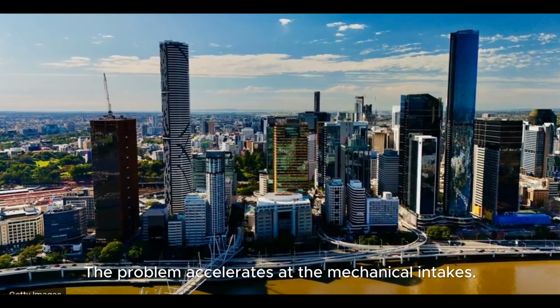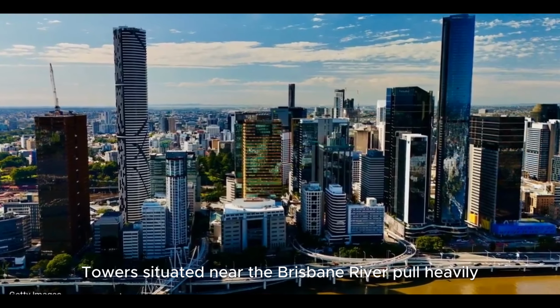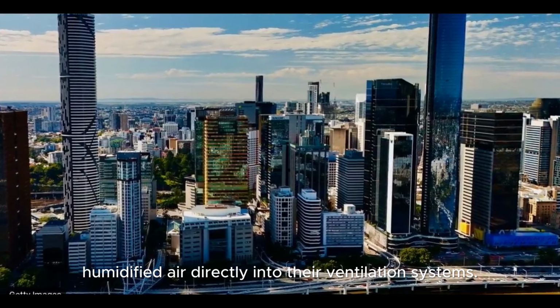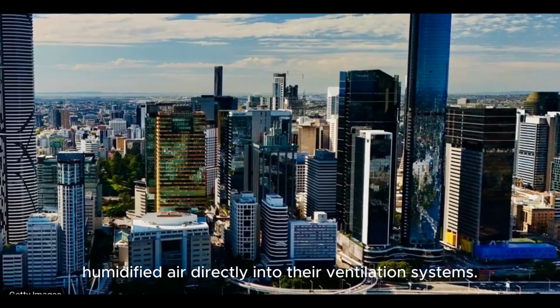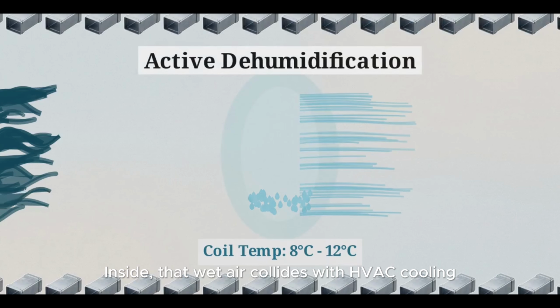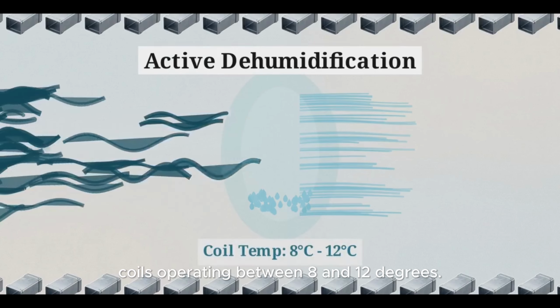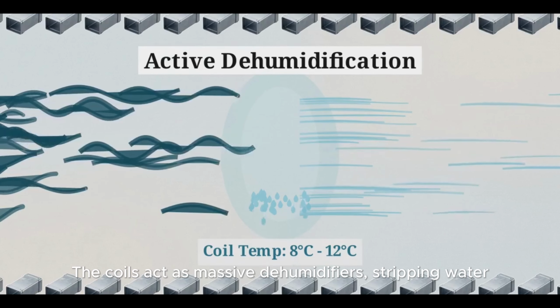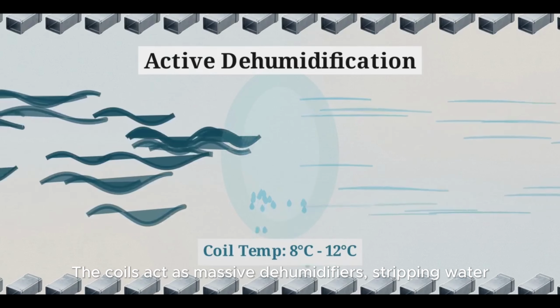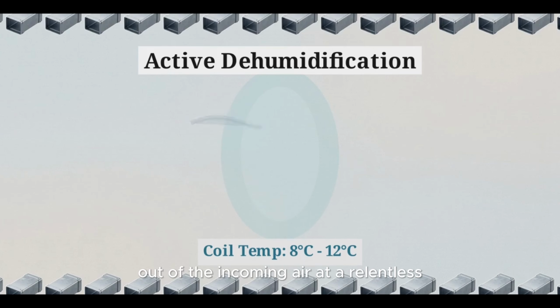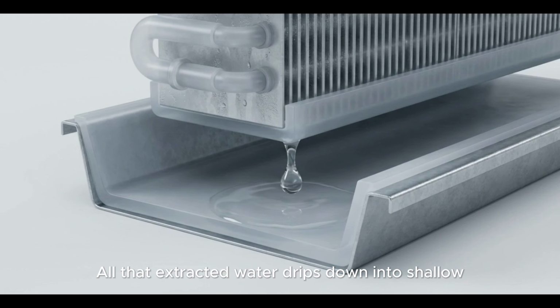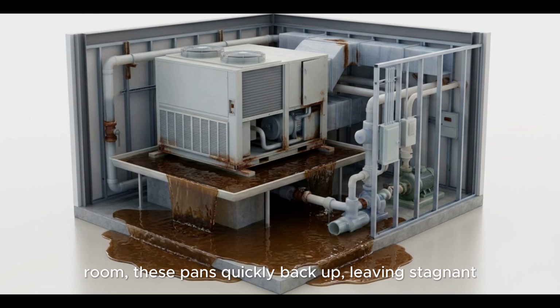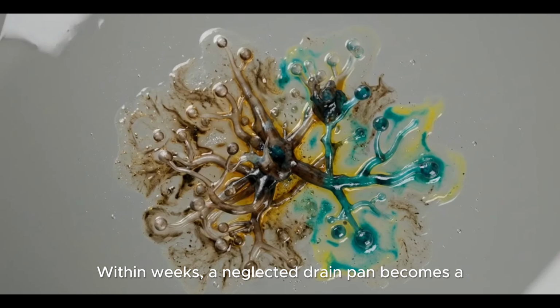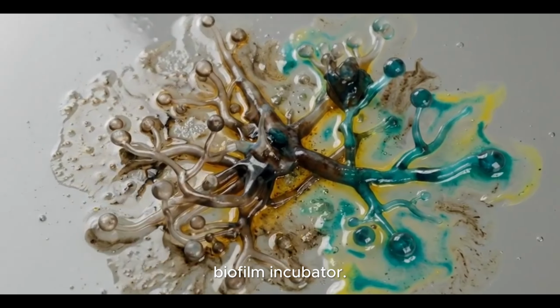The problem accelerates at the mechanical intakes. Towers situated near the Brisbane River pull heavily humidified air directly into their ventilation systems. Inside, that wet air collides with HVAC cooling coils operating between 8 and 12 degrees. The coils act as massive dehumidifiers, stripping water out of the incoming air at a relentless pace. All that extracted water drips down into shallow collection pans. In the ambient heat of an enclosed plant room, these pans quickly back up, leaving stagnant pools sitting in the dark. Within weeks, a neglected drain pan becomes a biofilm incubator.